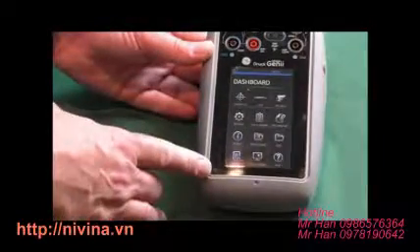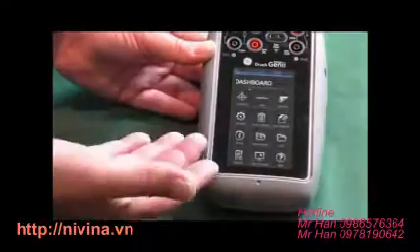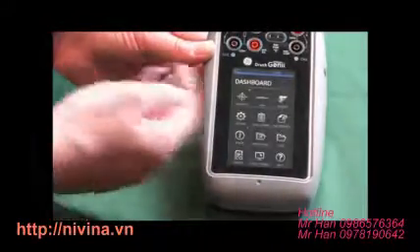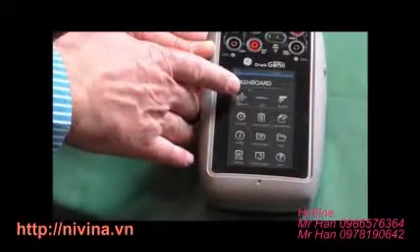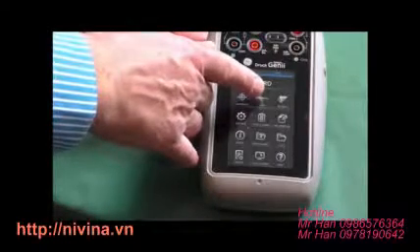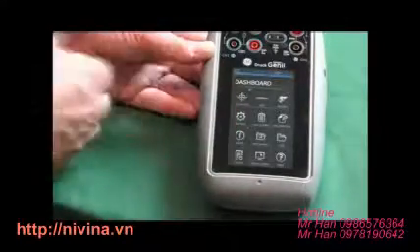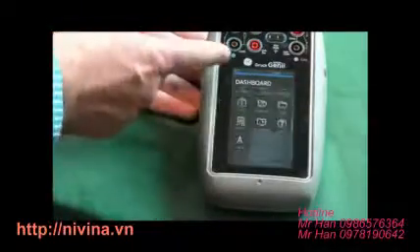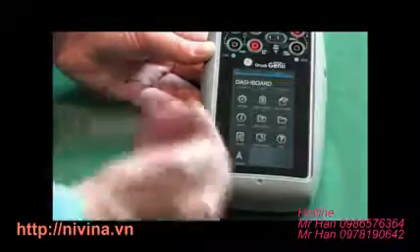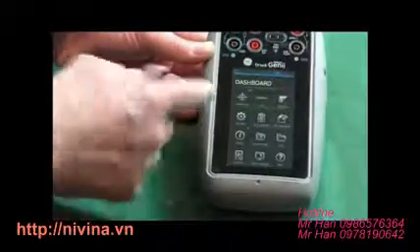Okay, so the GE has a capacitive touchscreen, so very much like your smartphone, which we're all used to, and it's very intuitive. So we have graphics on the front here. As you can see, at the moment we've got highlighted the calibrator, which is what I'm going to go into shortly. We also have the HART communication functionality, the fieldbus functionality. We get into our settings. We can look at the status, the software build, because we can upgrade this and do improvements to the software and upgrade it from time to time. We can scroll down, we get to our advanced settings where we get into our calibration features. So this is our front screen, and we can always get back to this by pressing the home button.